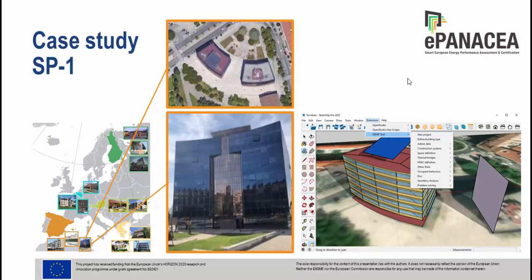The HVAC system is mainly composed of four condensing boilers for heating and one 350 kW chiller for cooling, located on the roof. Distribution and emission for heating and cooling is carried out by a four-pipe fan-coil system. The building is supplied by natural gas for heating and electricity for cooling, lighting, and other equipment. The lighting system has been replaced by LED lamps with daylighting dimming control and presence sensors, and a central BMS for building control and energy monitoring was installed in 2020.